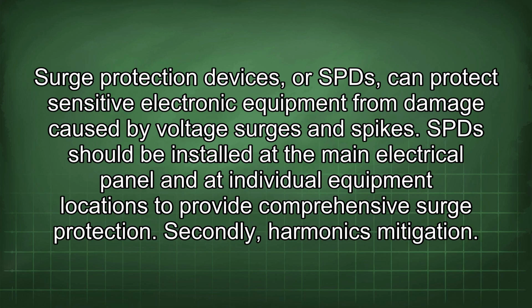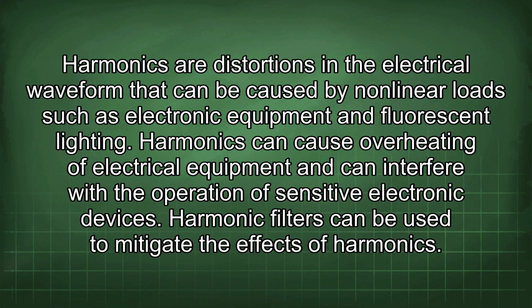Secondly, harmonics mitigation. Harmonics are distortions in the electrical waveform that can be caused by nonlinear loads such as electronic equipment and fluorescent lighting. Harmonics can cause overheating of electrical equipment and can interfere with the operation of sensitive electronic devices. Harmonic filters can be used to mitigate the effects of harmonics.